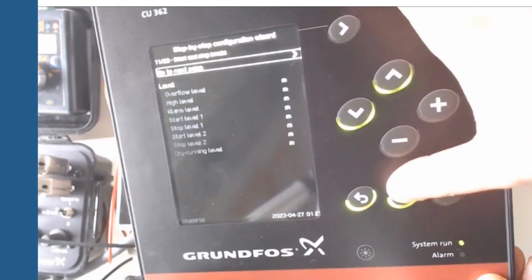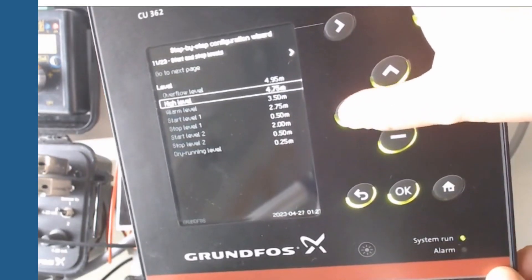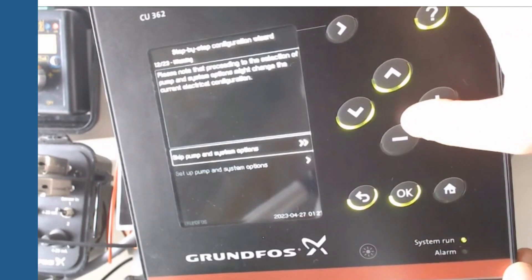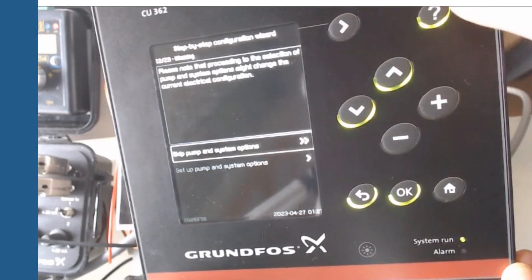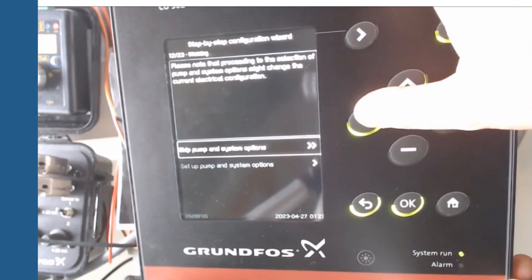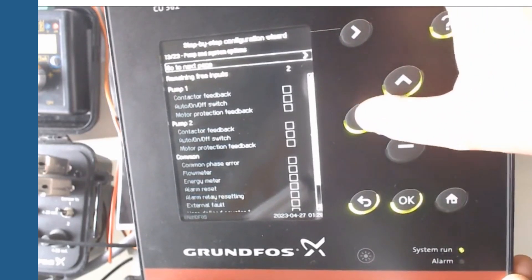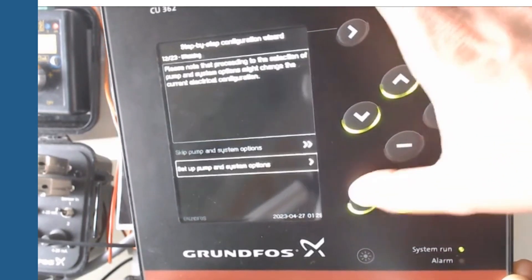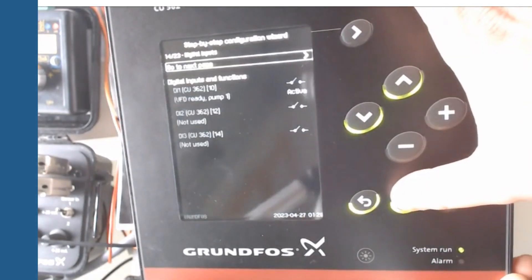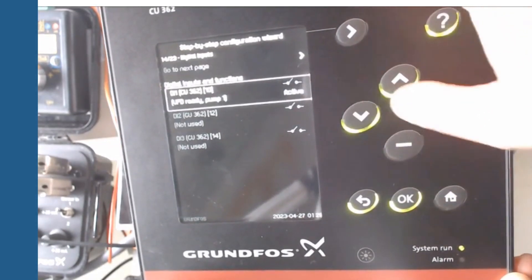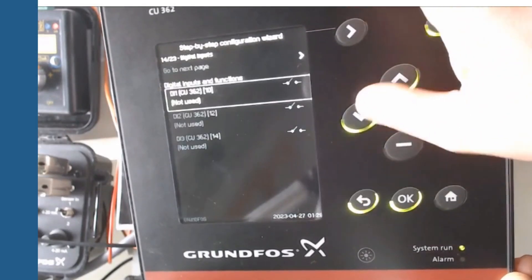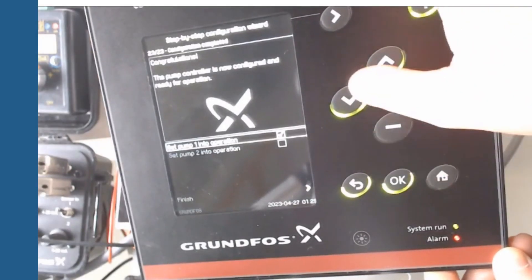Then is possible to set the start and stop levels to pumps, either the overflow and the dry running level. Through wizard it is possible to set some pump and system options. It can be used to adapt the panel and functions to the real system. In the example we skip the point. The wizard also offers digital input settings. After it pump controller was configured so we can set pumps in operation.